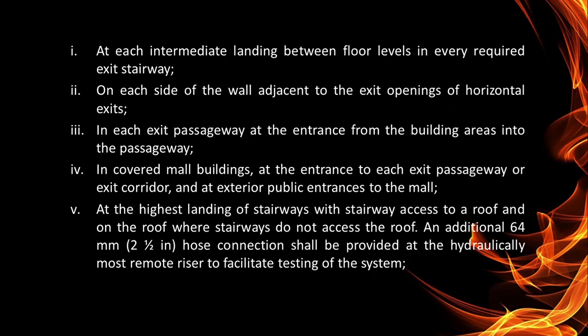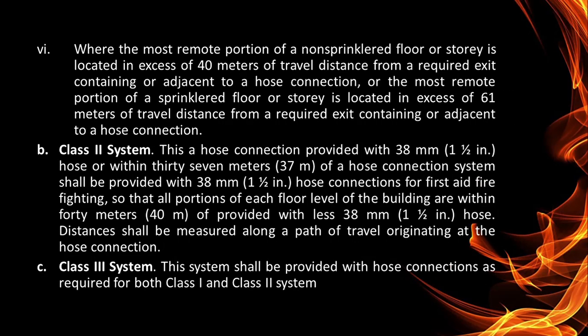An additional 64 mm or 2 1/2 inch hose connection shall be provided at the hydraulically most remote riser to facilitate testing of the system. Sixth, where the most remote portion of a non-sprinklered floor or story is located in excess of 40 meters of travel distance from a required exit containing or adjacent to a hose connection, or the most remote portion of a sprinklered floor or story is located in excess of 61 meters of travel distance from a required exit containing or adjacent to a hose connection.